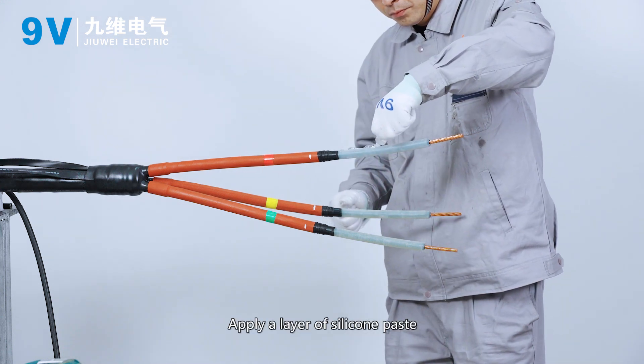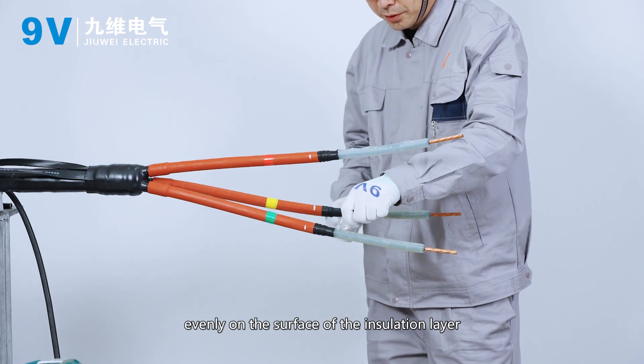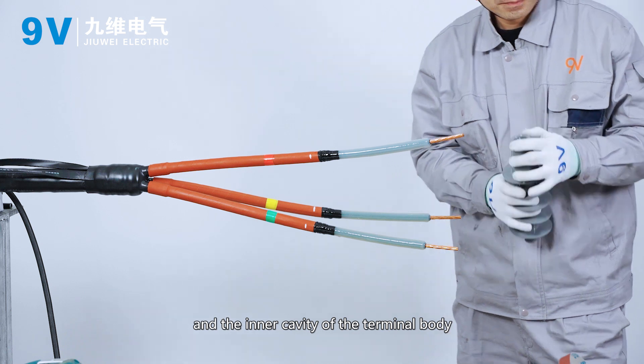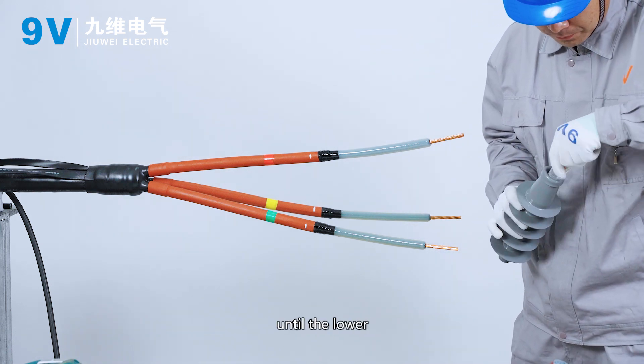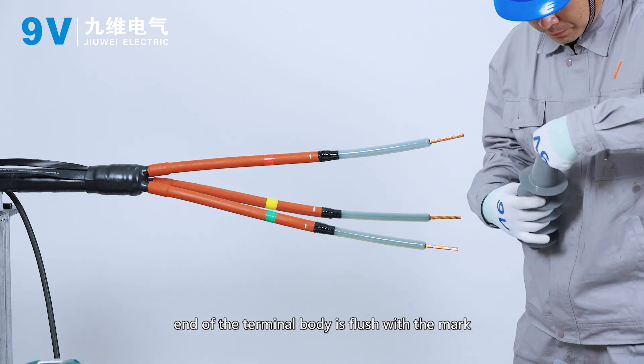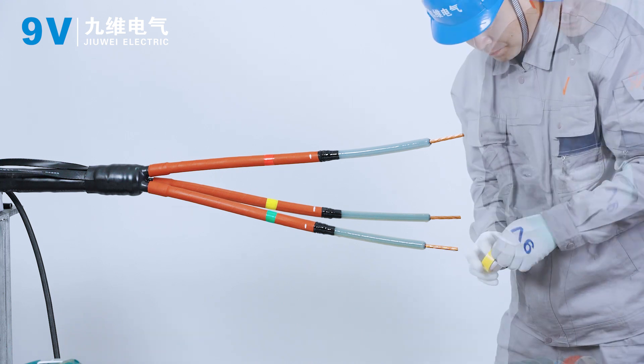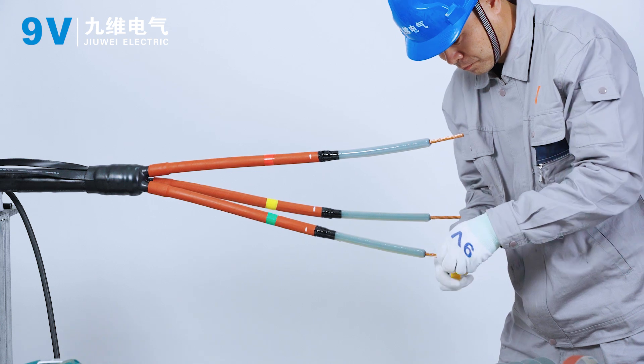Apply a layer of silicone paste evenly on the surface of the insulation layer and the inner cavity of the terminal body. Force the terminal body into the cable until the lower end of the terminal body is flush with the mark. Wrap the core end with PVC tape.